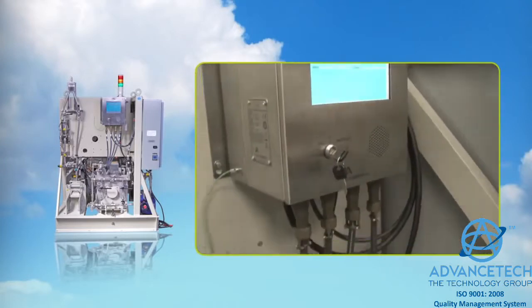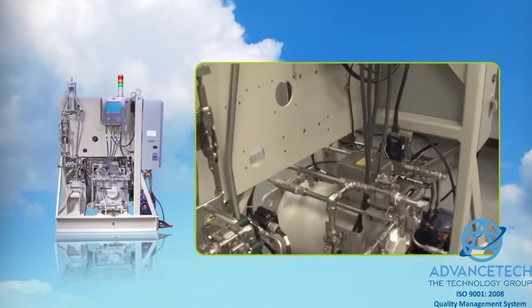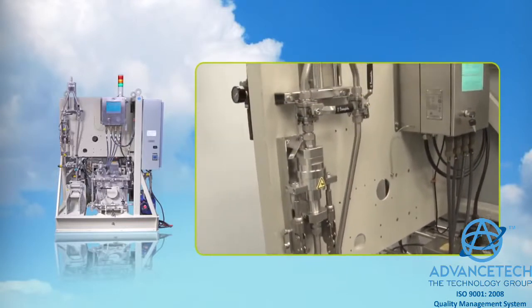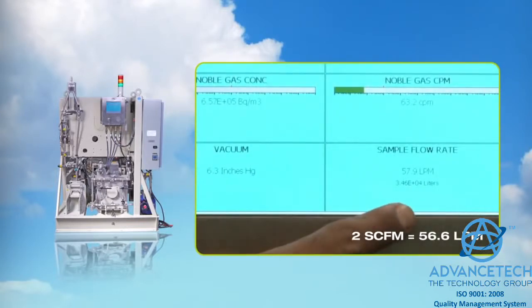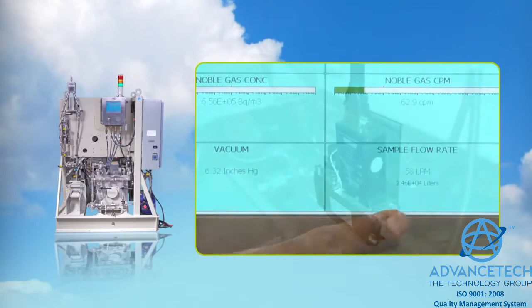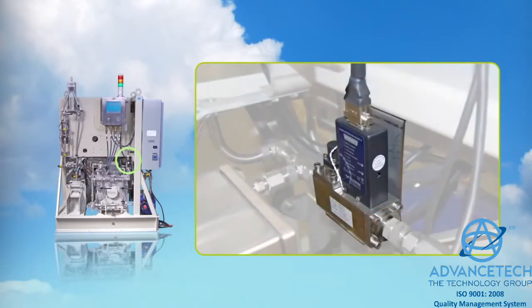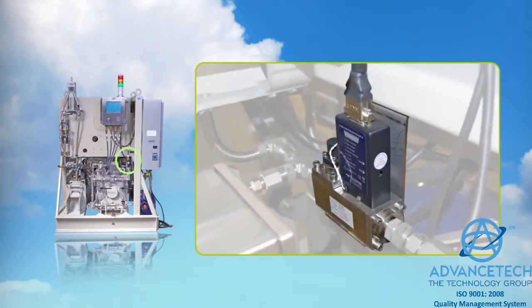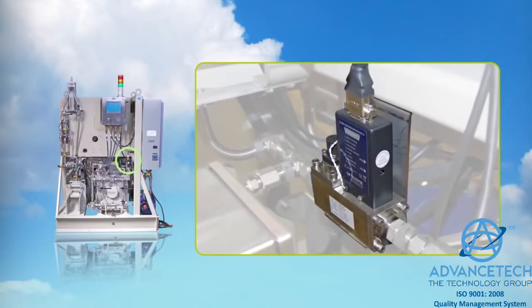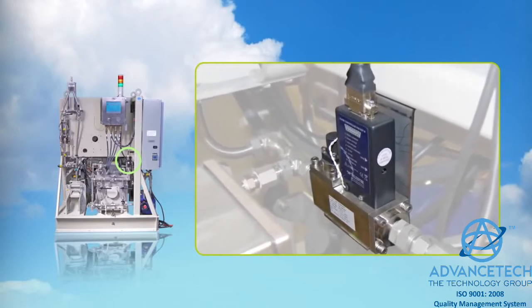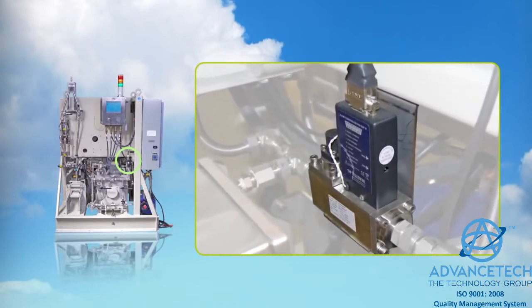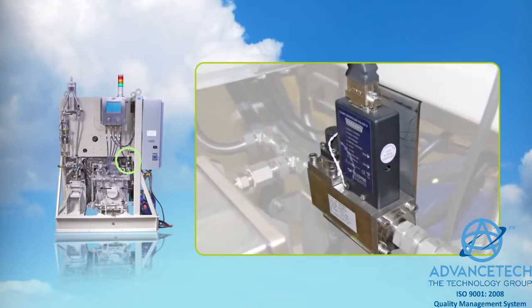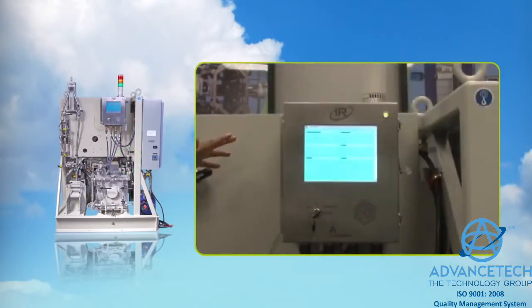To maintain collection efficiency, it is necessary to maintain the sample flow at 2 SCFM. Our system uses a mass flow controller that will open up the valve and continue to maintain a constant 2 SCFM flow during the filter loading that occurs during normal use between regular filter changes. As the system starts to clog, our system maintains constant 2 SCFM flow until it is completely clogged. At that time, it gives a low flow alarm.